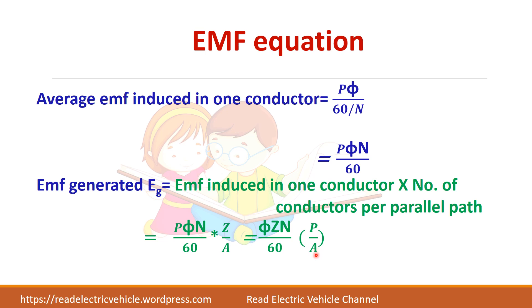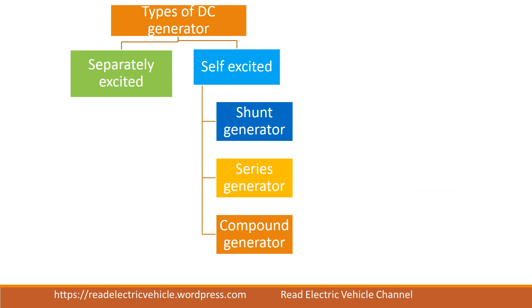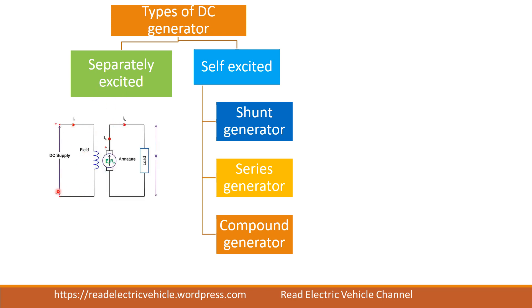Depending upon whether it is lap winding or wave winding, the value of A will change. You can substitute A equal to 2 for wave winding or A equal to P for lap winding. Now let us see about the different types of DC generator. Basically there are two types: separately excited generator and self-excited generator. Excitation means field. When the field is given a separate DC supply, we call it a separately excited generator. In self-excited generators, there is no separate supply for the field winding — the machine itself will supply the field. There are three types: shunt generator, series generator, and compound generator.